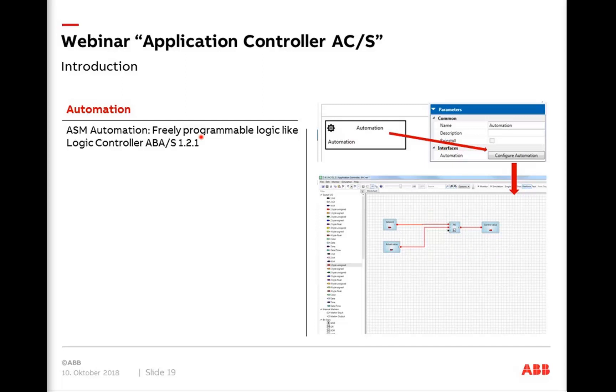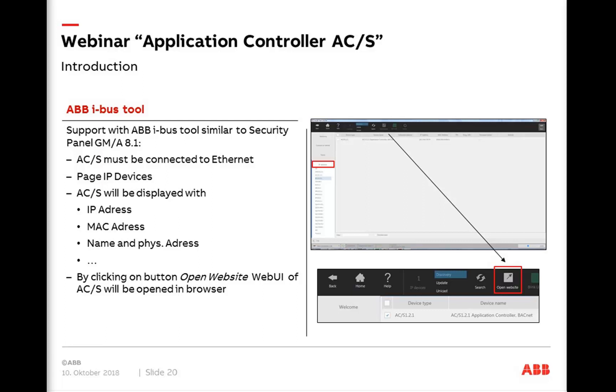The freely programmable logic is similar to the logic controller ABA/S 1.2.1 — it's one ASM. You select the automation ASM and click 'configure automation' to open the worksheet, where you create your own logic using existing modules: logical functions, comparisons, mathematical functions, PID controller, and more. You then go back to the ETS and integrate it into your complete application controller setup.